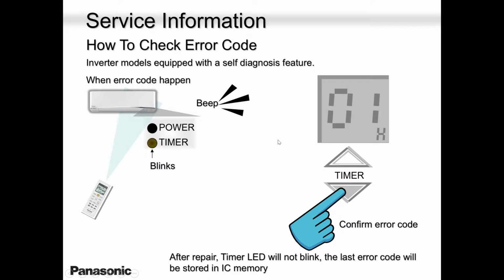Because mind you, there is only one error code stored in that remote controller, or stored in that chip of the indoor unit, that it will beep on. And I'll tell you, 99.9% of our error codes were accurate. I don't want to say 100 because you'll say, oh, Paul, you're bragging now. But the fact is, 99.9% of all error codes that came off that indoor unit EEPROM were the problem. And I'm saying 99.9% because I'm comparing with our other friends. When you get an error code, it might not be the same problem. It might be a different problem.